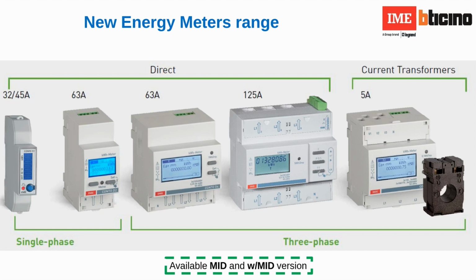So our range of energy meter, basically, we have a 1 module DIN mounted single phase up to 45 ampere direct connection. We have also single phase 2 module direct connection up to 63 amp. Then we go to the 3 phase direct connection up to 63 amp, but in 4 DIN modules. And then we have also a reference that can measure a nominal current up to 125 ampere, 3 phase. In this case, it's 6 DIN modules. Then, of course, we have the indirect model, the one that accepts external current transformers.